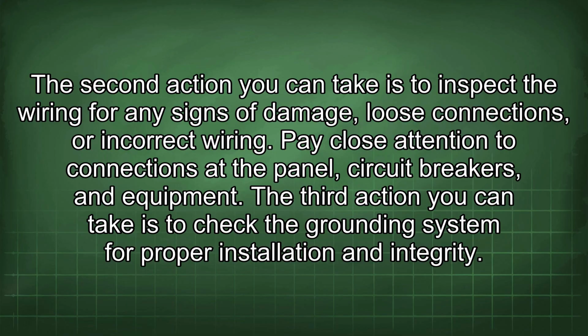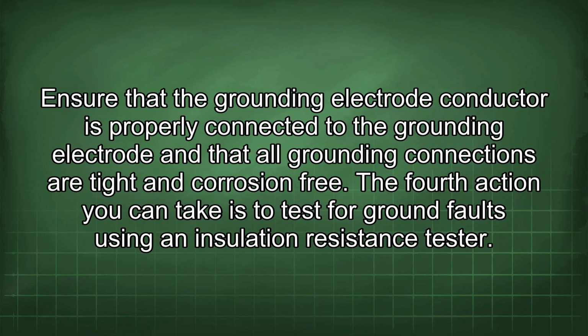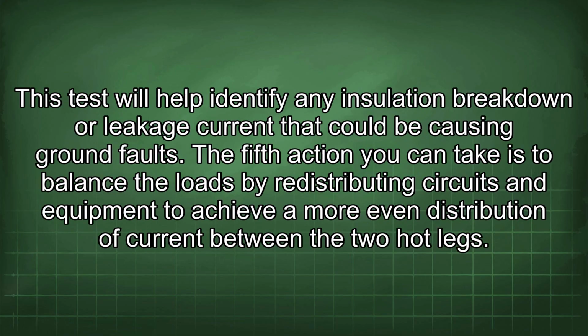The third action you can take is to check the grounding system for proper installation and integrity. Ensure that the grounding electrode conductor is properly connected to the grounding electrode and that all grounding connections are tight and corrosion-free. The fourth action you can take is to test for ground faults using an insulation resistance tester. This test will help identify any insulation breakdown or leakage current that could be causing ground faults. The fifth action you can take is to balance the loads by redistributing circuits and equipment to achieve a more even distribution of current between the two hot legs.